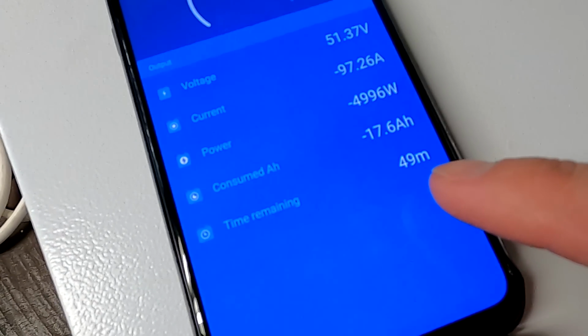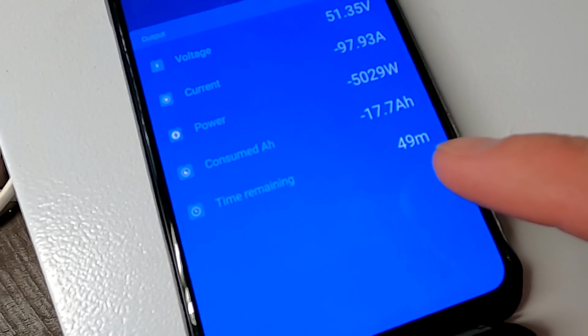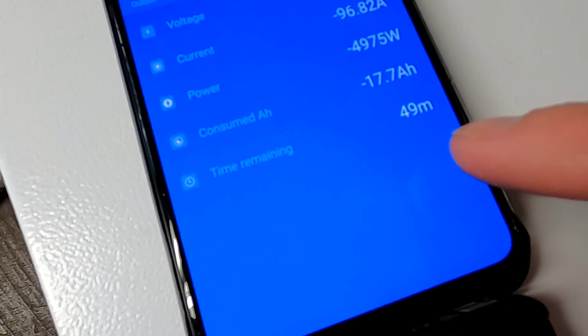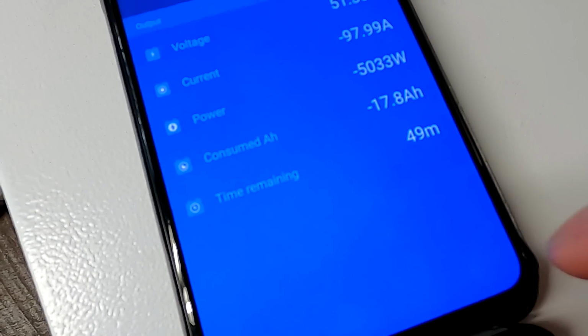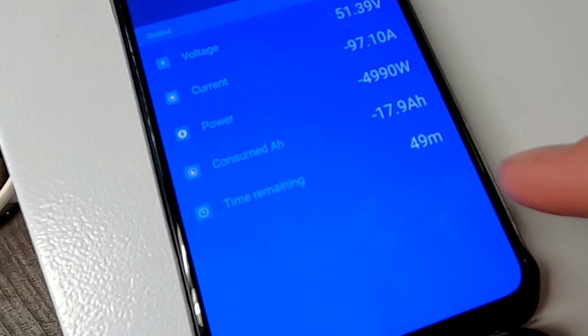Okay, the shunt actually tells us we've got only 49 minutes until we are empty. Oh wow, that is very pessimistic. I mean, it's a 280 amp hour battery, and if you pull 100 amps, that should give us at least 2 hours, 2.5 hours, but 49 minutes.